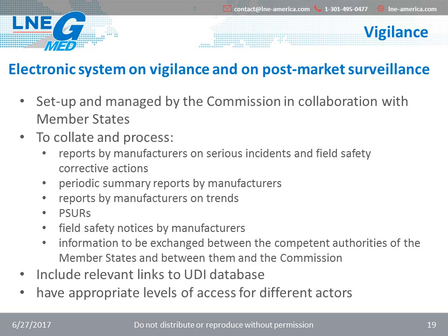The goal of this electronic system will be to collate and process reports by manufacturers on serious incidents and field safety corrective actions, periodic summary reports by manufacturers, reports by the manufacturers on trends, PSURs, field safety notices by manufacturers, and information to be exchanged between the competent authorities of the member states and between them and the Commission. The system will also include links to the Unique Device Identifier, or UDI, database.